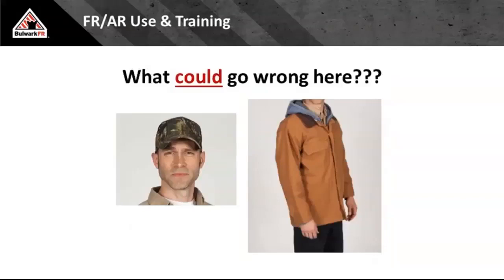What can go wrong here? Now, a lot of our general industry electricians do work outside. They do work in weather. You have a very expensive arc-rated coat here, and that hoodie. You see that hoodie up around the neckline, the back of the head there? My question to you is, is that arc rated? Because now it's the outermost layer. What do our standards tell us about arc-rated clothing? Always the outermost layer. Once that comes outside of that jacket, it needs to be arc rated. If it's not, you potentially have a lot of fuel sitting on the back of your head.